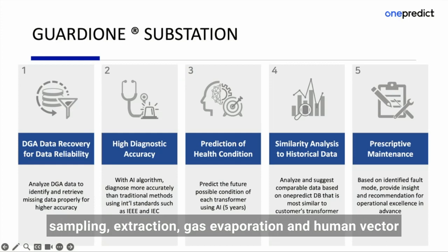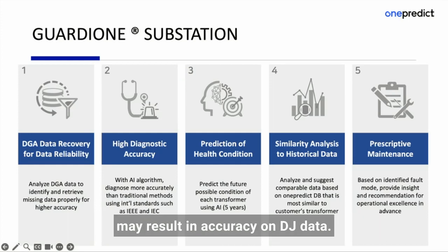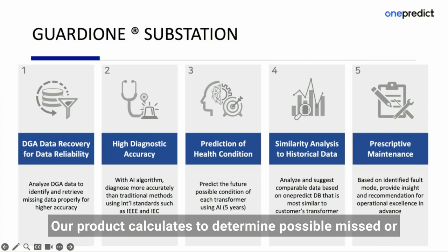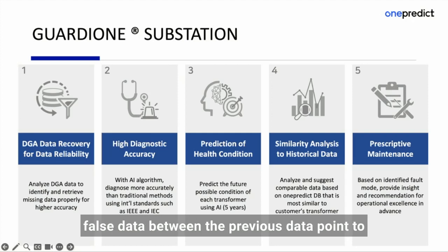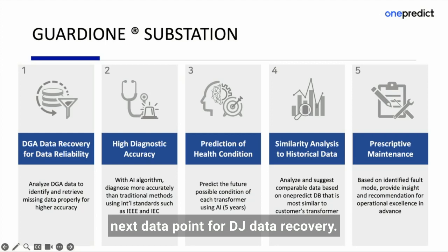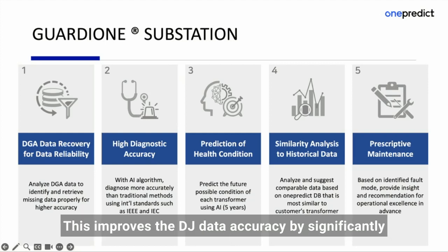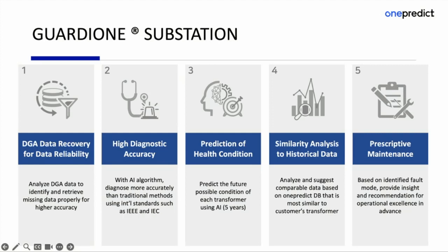During sampling extraction, gas evaporation and human factors may result in inaccuracy in DGA data. Our product calculates to determine possible missed or false data between the previous data point and the next data point for DGA data recovery. This improves the DGA data accuracy significantly.